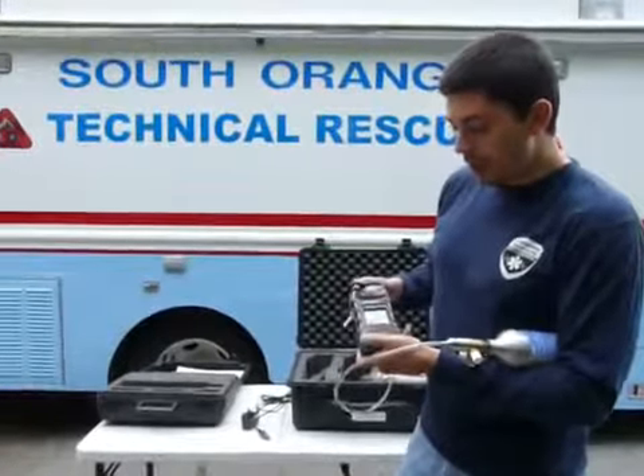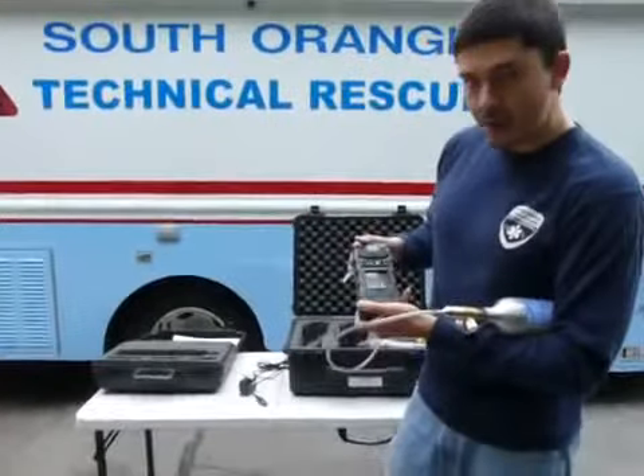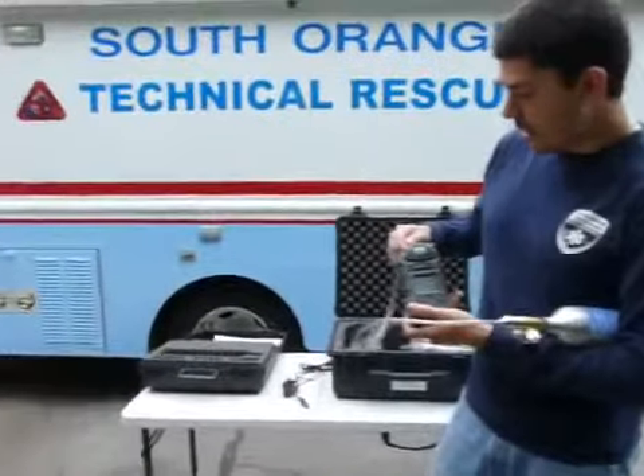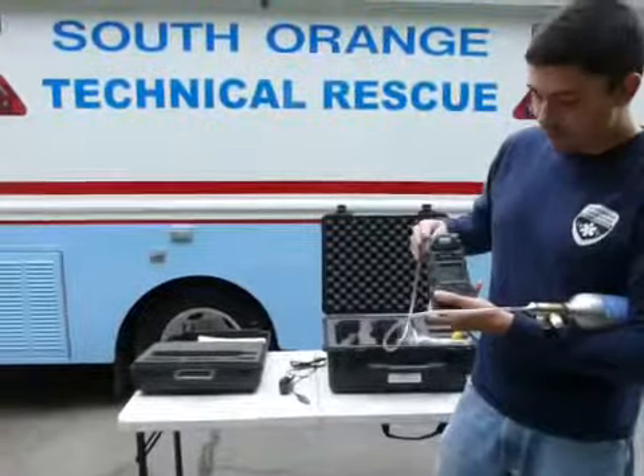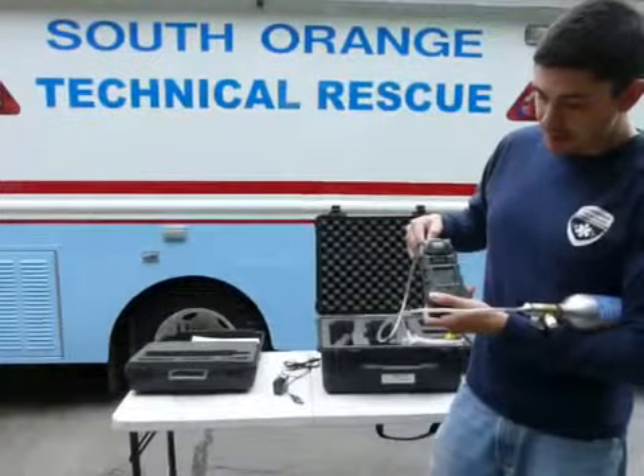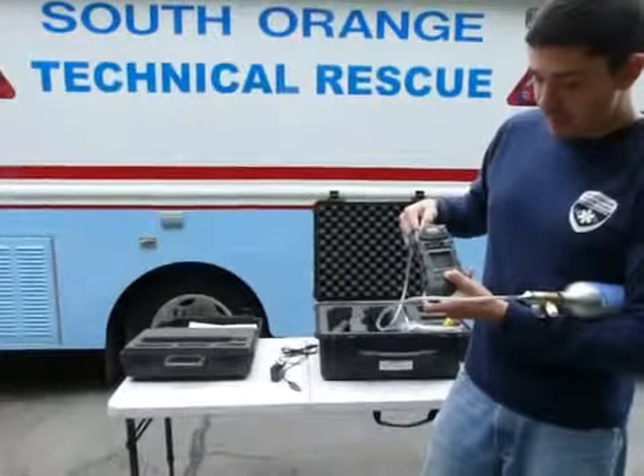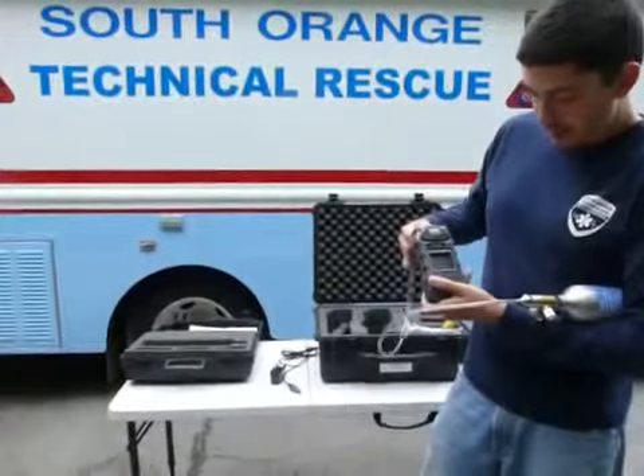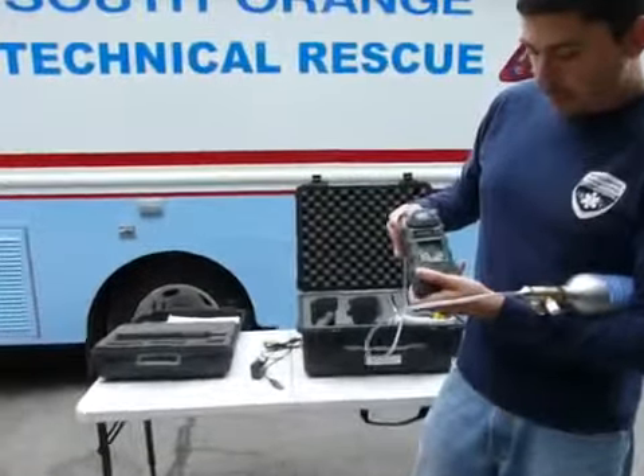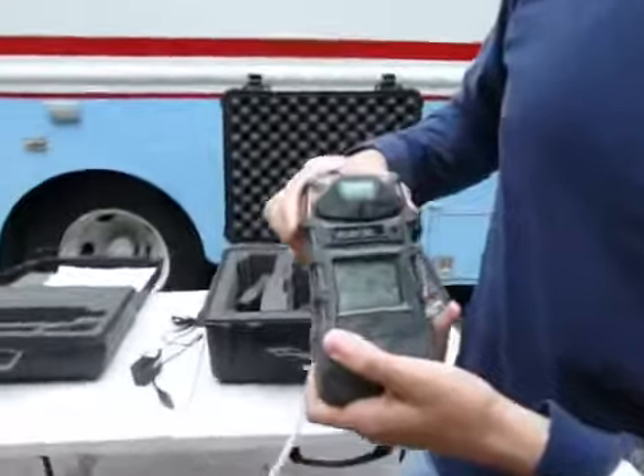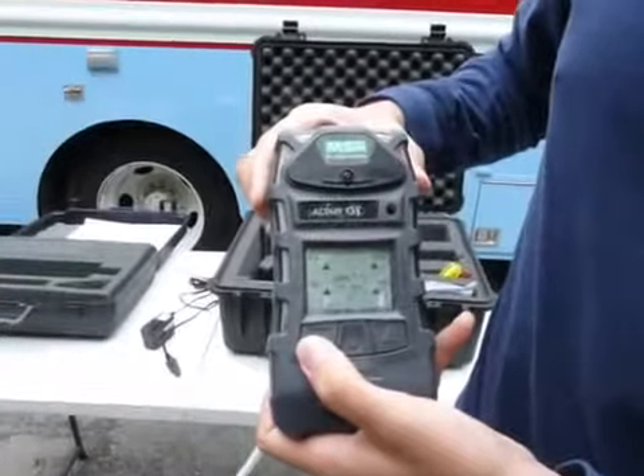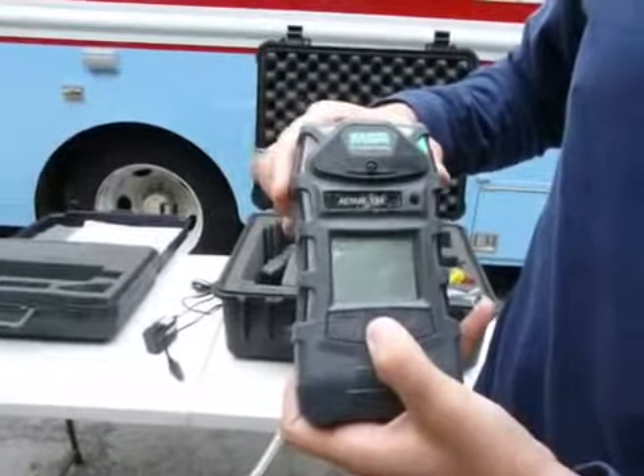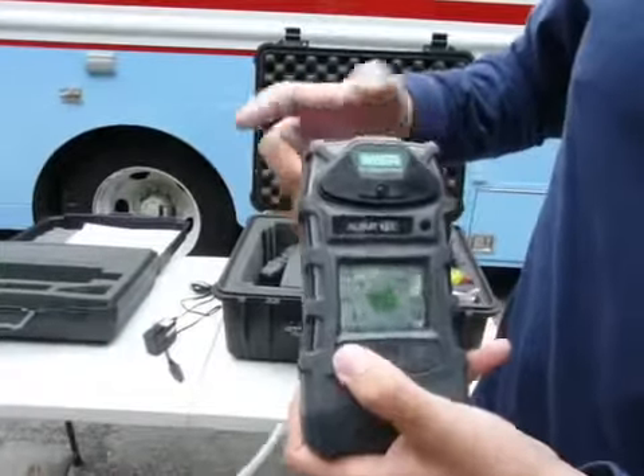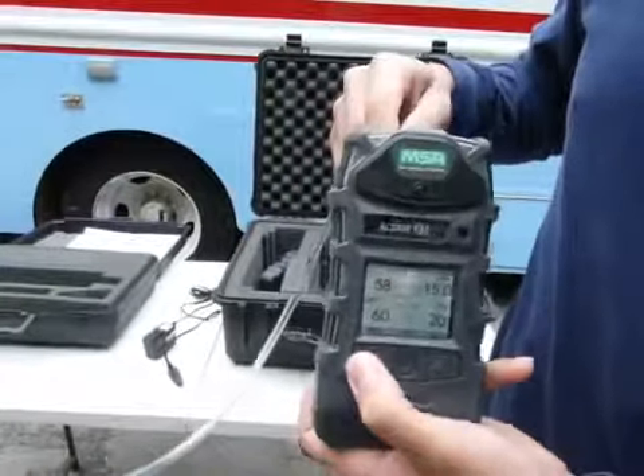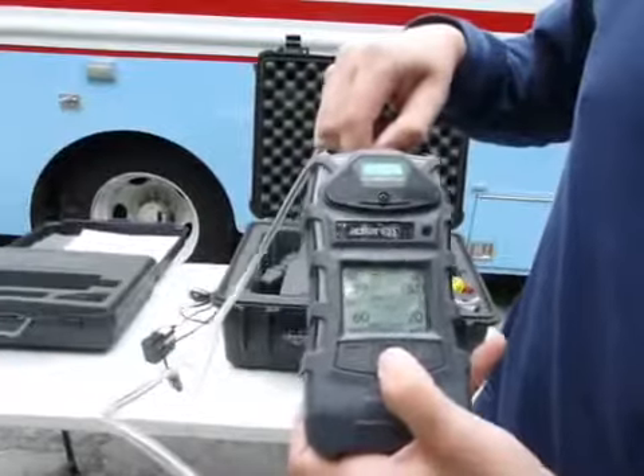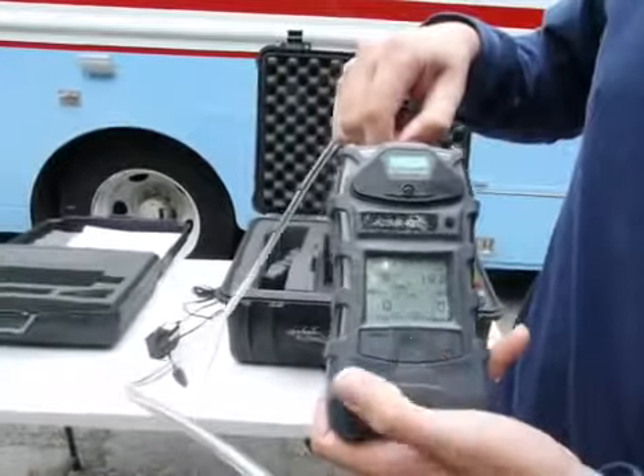Now I'm going to push the bump button again, which is just a simple push of the down arrow. And I'm going to put the tubing from the calibration gas close to the unit itself. I'm going to hit yes for the bump test. And here it didn't appreciate it because I put it too close to the unit too quickly. I'm going to push bump again. I'm going to hit yes for the bump test.